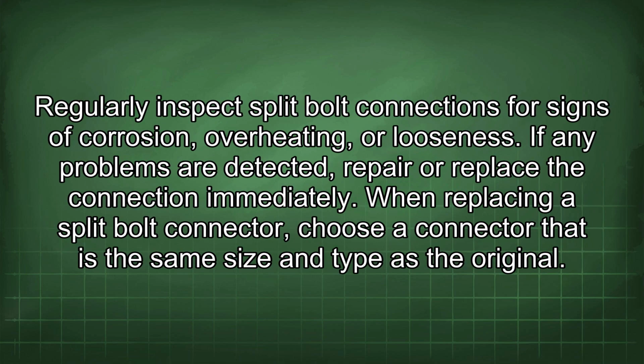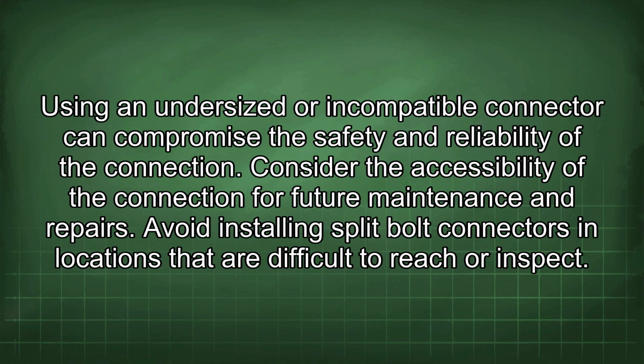Regularly inspect split bolt connections for signs of corrosion, overheating, or looseness. If any problems are detected, repair or replace the connection immediately. When replacing a split bolt connector, choose a connector that is the same size and type as the original. Using an undersized or incompatible connector can compromise the safety and reliability of the connection.